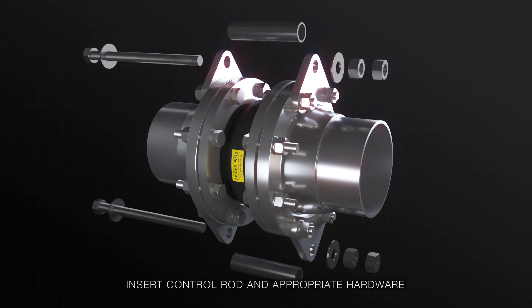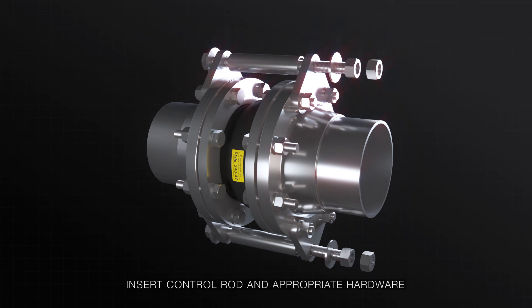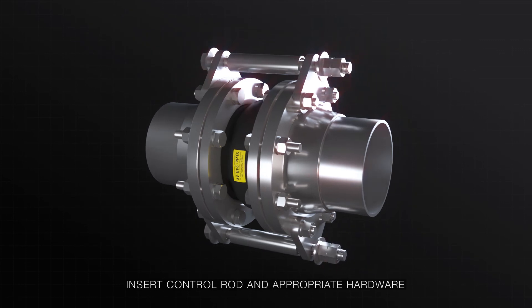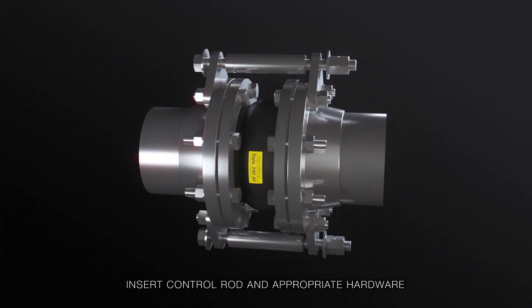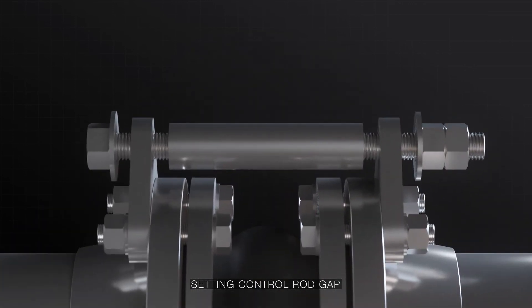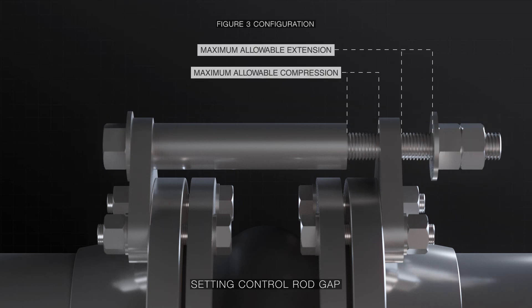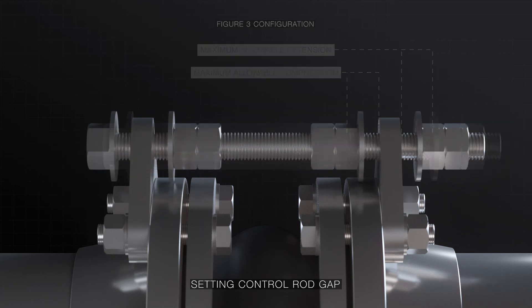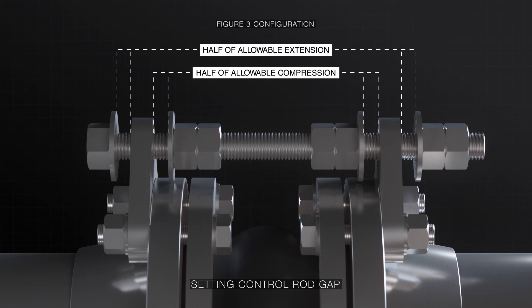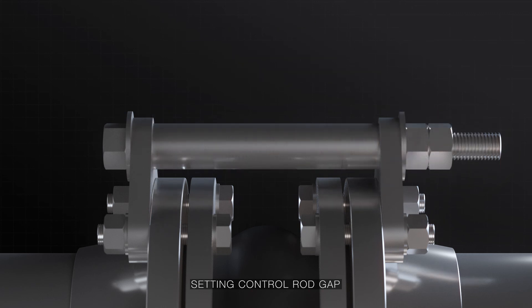Insert the required control rod through the control unit plates and add the appropriate hardware for your configuration. Ensure the control sleeve is cut to the appropriate length as per the user manual. Finally, set the control rod gaps for the nuts and compression sleeve length. The outer and inner gaps should meet the maximum extension and maximum compression requirements. Unanchored systems should not have gaps, and the nuts should fit snugly.